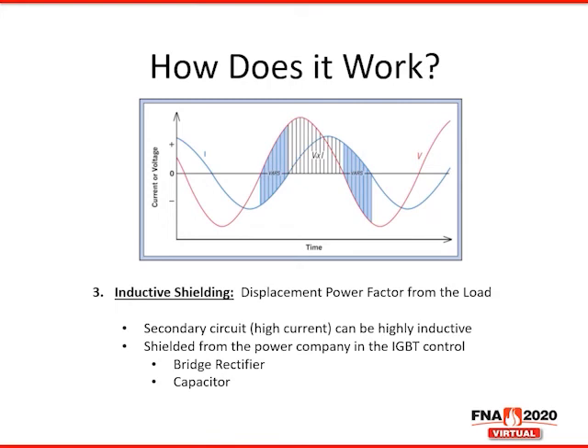Our third source of efficiency is inductive shielding. So what is inductive shielding? The graphic here shows how current can lead or lag from the application of voltage, depending on how much capacitance or inductance you have in the system. An ideal power factor is when the current waveform is directly over the voltage waveform, and that would correlate to a displacement power factor of near unity. Effectively, with our IGBT MFDC control, with the rectification, the capacitance, and the inversion, we shield that highly inductive secondary load on the heating element side from the power company. So we see a power factor of near unity at any set point.